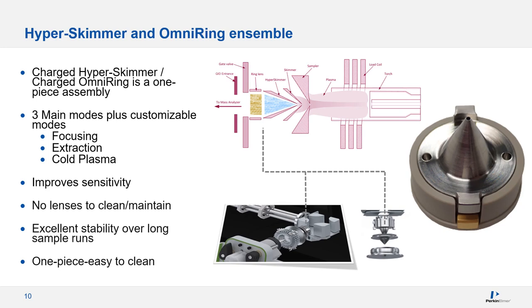The other notable addition to the Nexion 5000 is the OmniRing technology, which allows a voltage to be applied behind the hyperskimmer to optimize ion flow from the plasma, enhancing sensitivity and allowing analysis in different modes of operation: extraction, focusing, cold plasma, and customizable modes. The unique design of the OmniRing provides a more stable design compared to the multiple-plate lens design and also allows for easy removal and cleaning when needed.